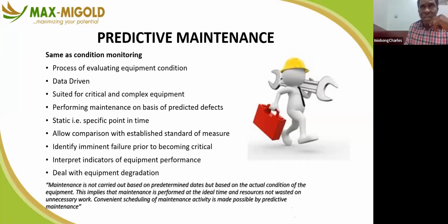You go and test it and say, okay, the oil is still good. You continue to run the generator. After some time you take it again, you test the oil, and you come up with a result and say, oh, it's still okay, we can still run for another hour. You are generating data, and with that data, you can take a decision. And maybe you take the oil again for testing and say, oh no, the usefulness of that oil is no more there, so you need to change it.